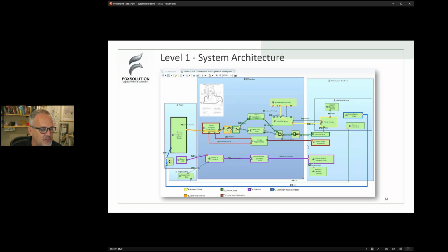And then that function would be interrelated with the rest of the functions in the device to decide what we're going to do with that data. What are the algorithms it's going to take advantage of? How is it integrated with the device itself? But in this case, because it's delivered by the clinician, it doesn't have anything to do with the ventilator at all. And so these are the decisions at the design level that we start to make: literally what's in the box, what's out of the box, what's in the device we're selling, and how does that relate to the design space in general.